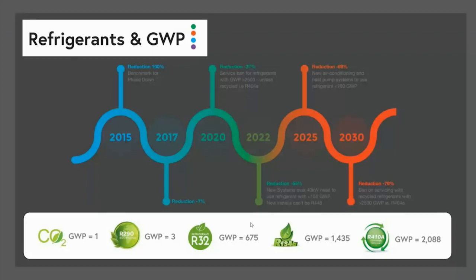Both R290 and CO2 are considered natural refrigerants. R290 is a hydrocarbon. It has got a GWP of 3. Then we've got the current industry standard, R32, which sits at 675. And then we've got some of the older ones that are in lots of existing appliances, so R134A and R410A. You can see they're 1435 and 2088, respectively.